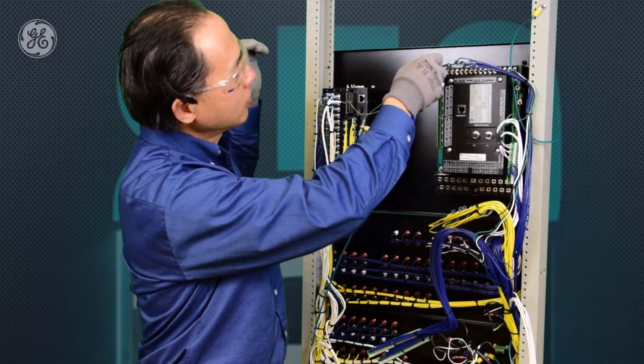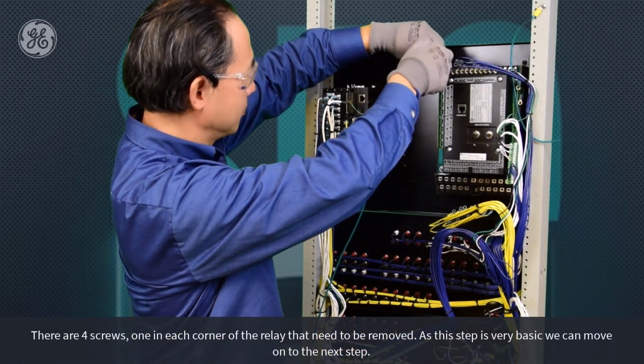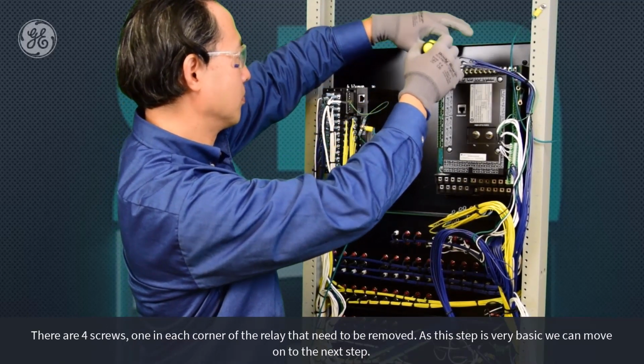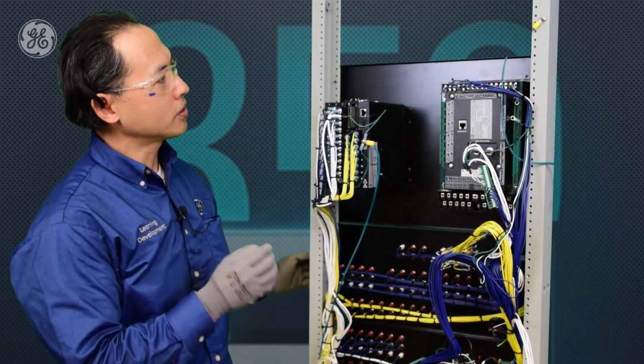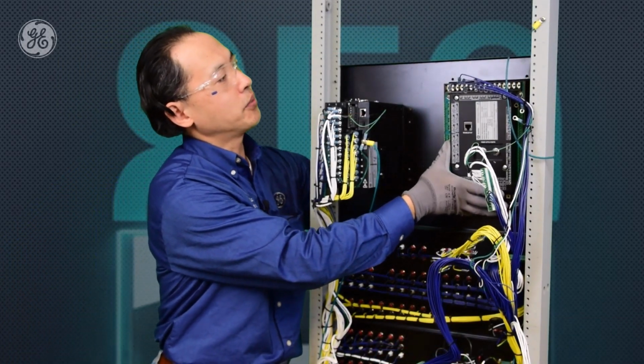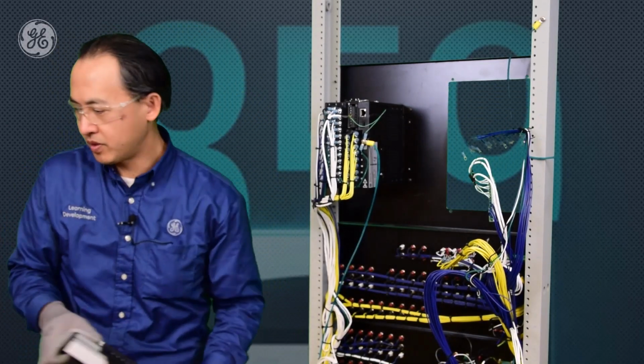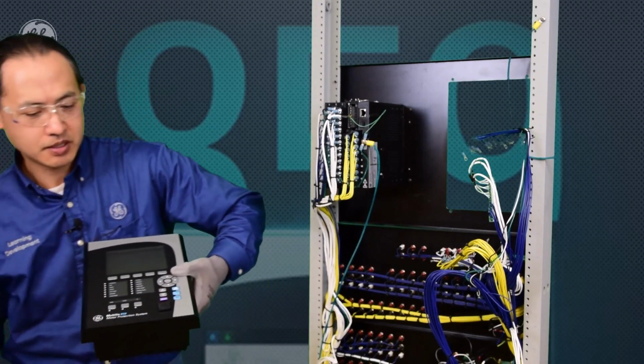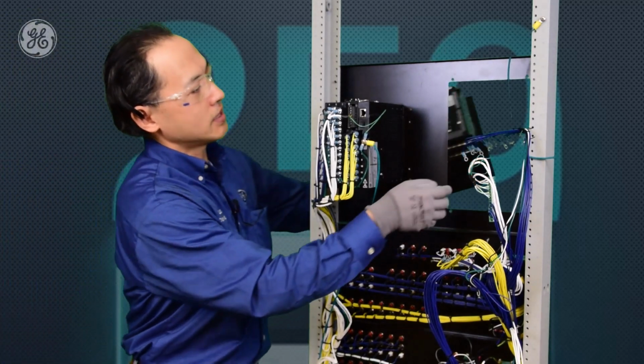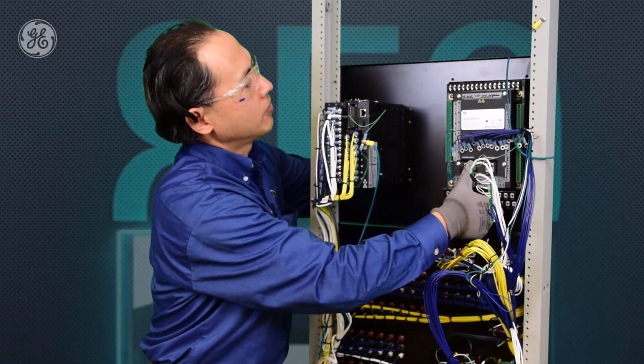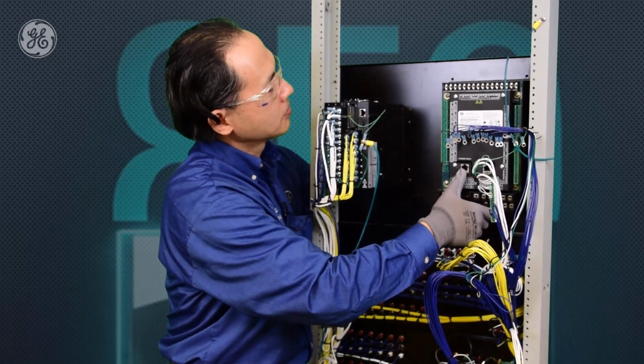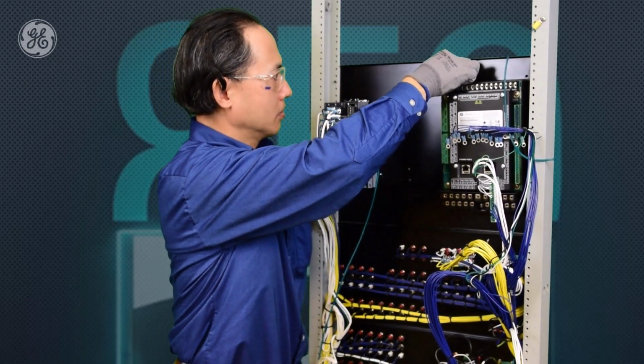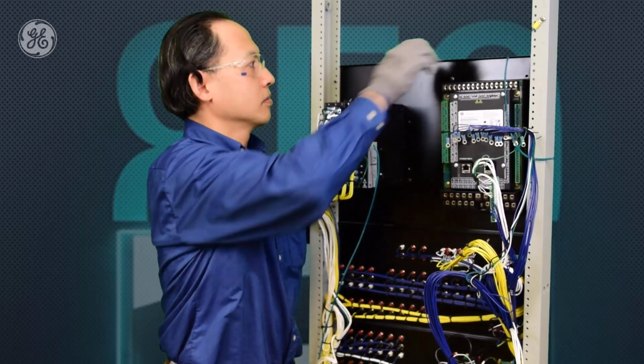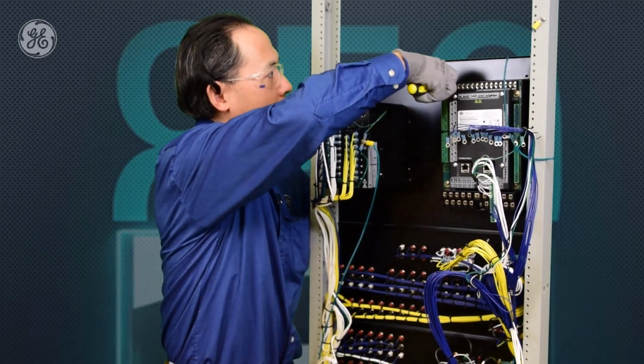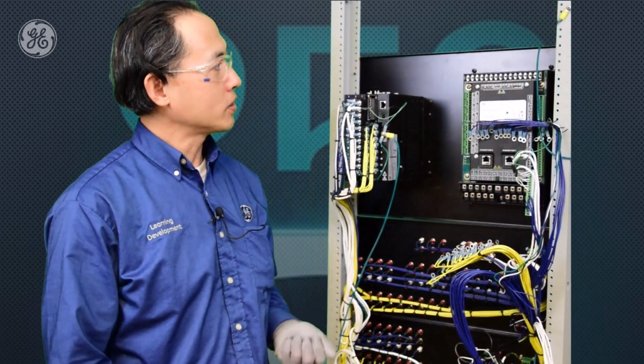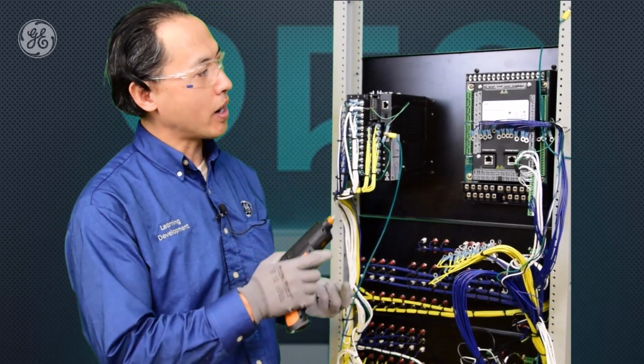We're going to remove these mounting screws on the panel. Now the 4 mounting screws are removed. We can gently remove this 369 relay from the rack and replace it with one new 859 relay. So this is the 859 we're going to put in the rack with the same cutout. And the first step is to put on the mounting screws. Once we put the screws back on the mounting rack, we're going to rewire the relay.